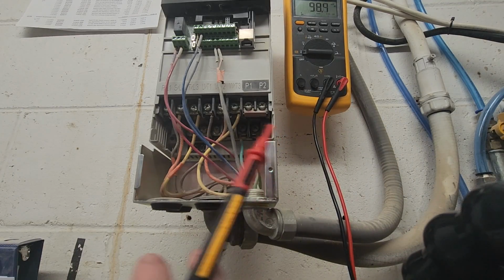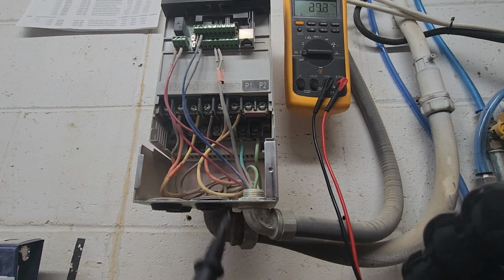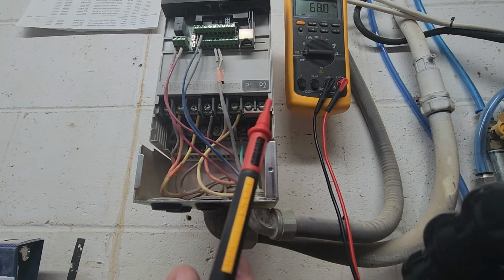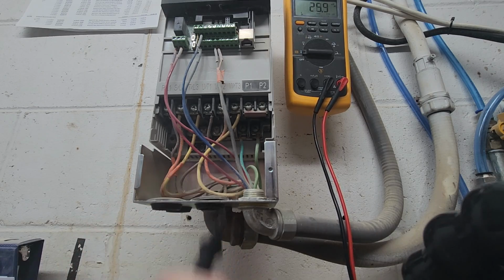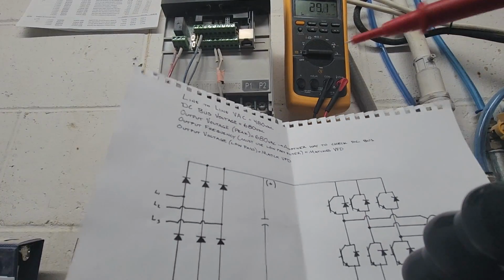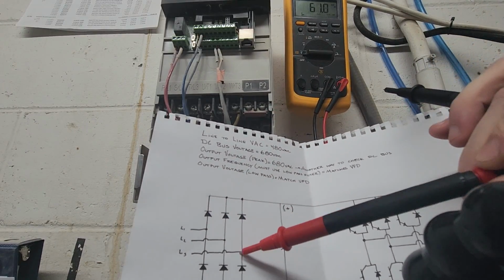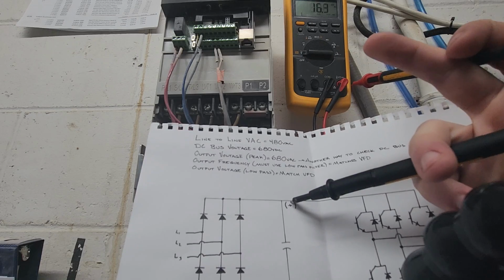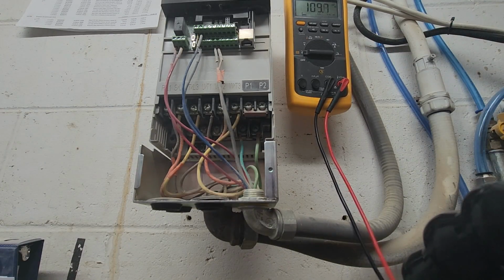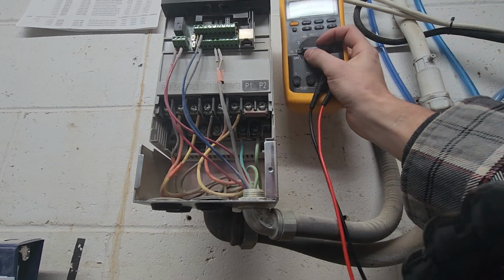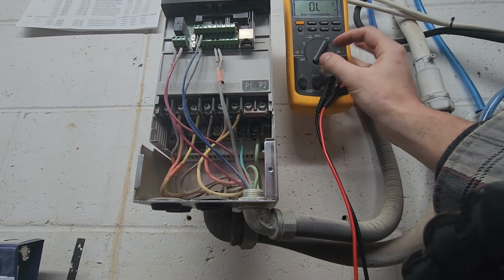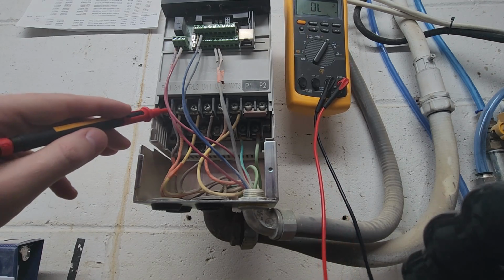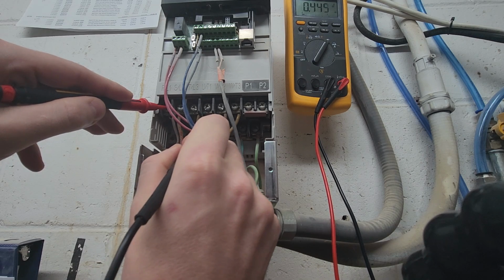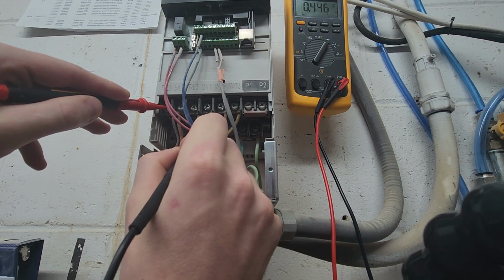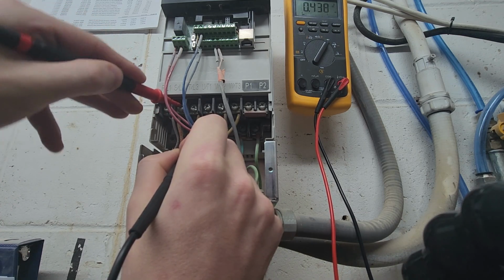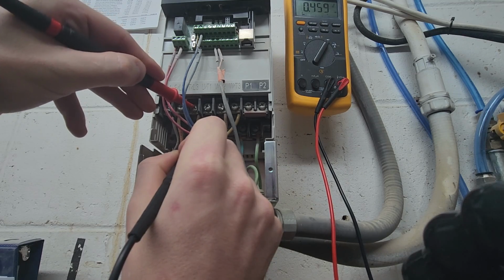But what we're gonna do, your red electrode on your multimeter has actually got the power, and your black one is looking for power. So think of this as your pixie stick and as your search instrument. We're going to put our meter into diodes, and we'll put our positive lead on L1, L2, and L3, and we'll have our negative on the DC bus positive, looking for voltage or looking for a good diode. So, one sec here, I'll flip my meter into diode. What did I say I was going to do? L1, the DC bus positive. We've got 0.4, yep, that's fine. 0.4, these numbers should all be the same. All right, that's all good.